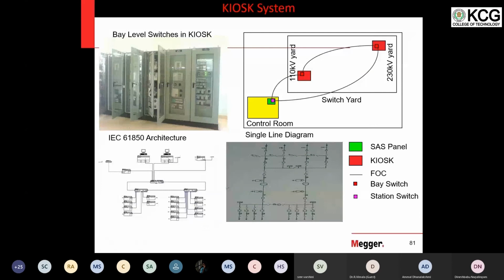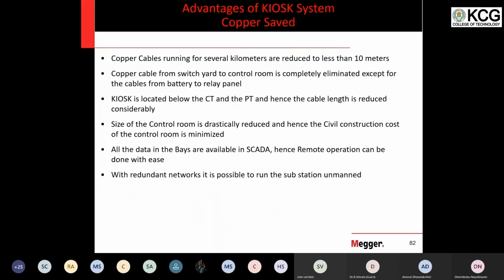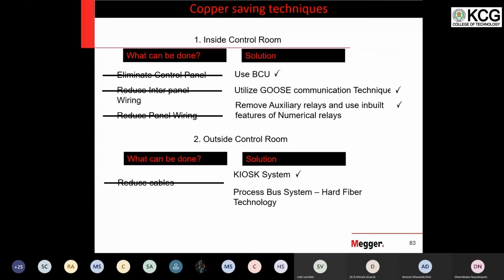What is this? FOC, fiber optic cable. So from this, what we understand is that between the control room and switchyard, there is only fiber optic cable. And that is what we were planning for in the initial slide. We want to eliminate the copper cable. Therefore, we have several advantages. This is the beauty of the kiosk system.